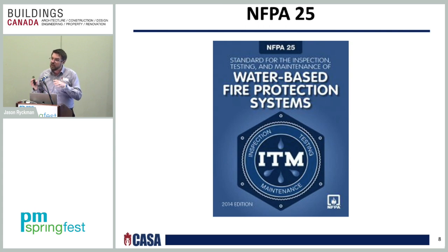One thing that you can't get confused with is the use of the installation standard as well as NFPA 25 whenever you are inspecting, testing, and maintaining. The only time that you use the installation standard is whenever you have any renovations, additions, or if you have any deficiencies that have to be repaired for some reason. That would fall under the installation standard and not the NFPA 25 standard, which is the inspection, testing, and maintenance document.